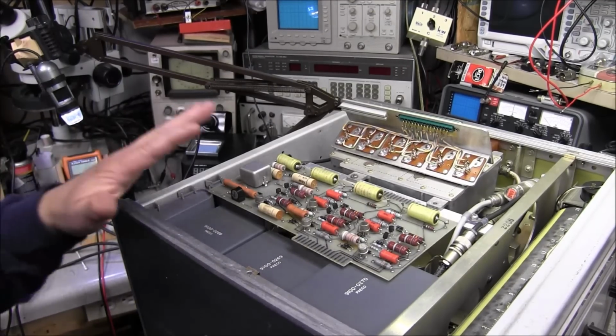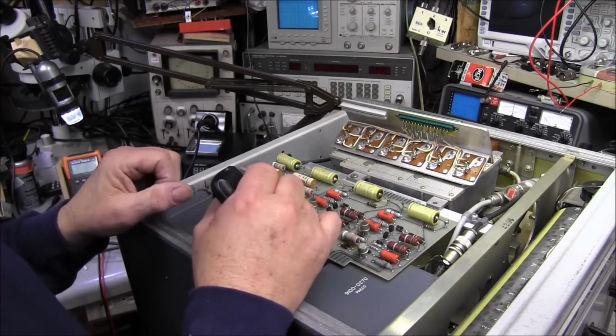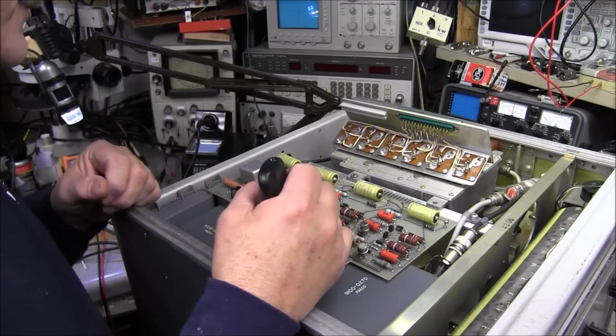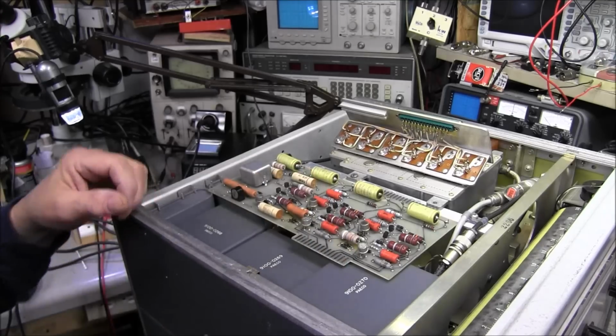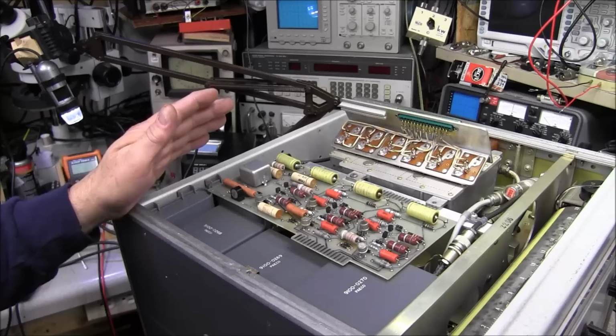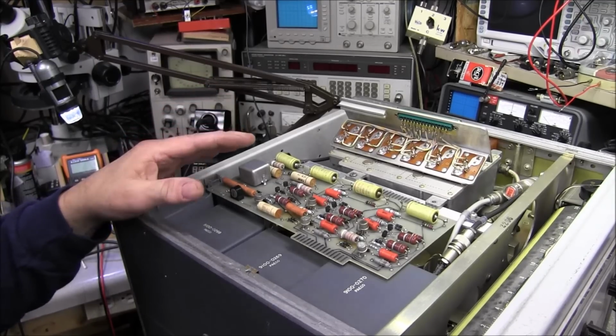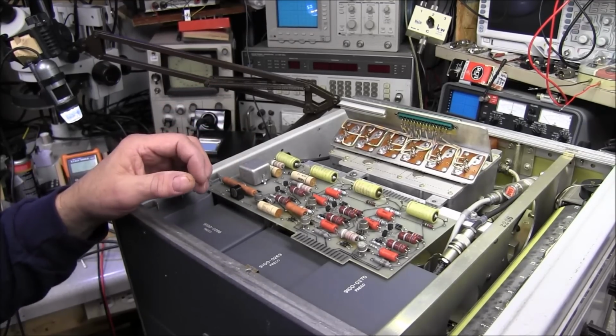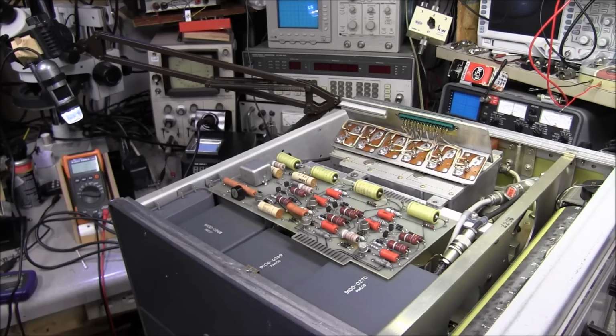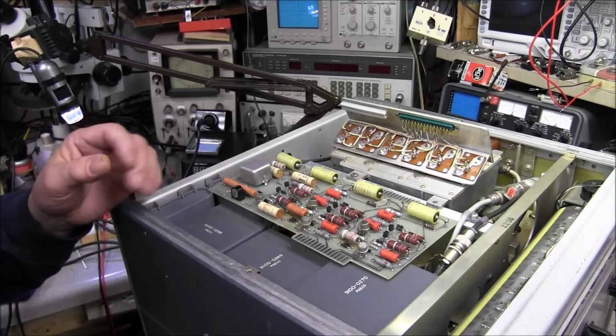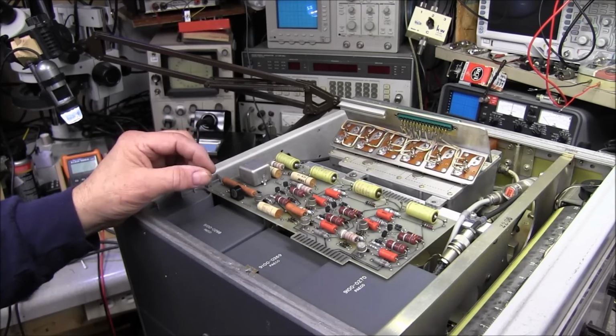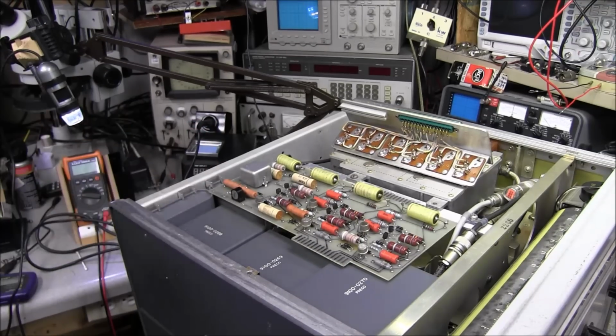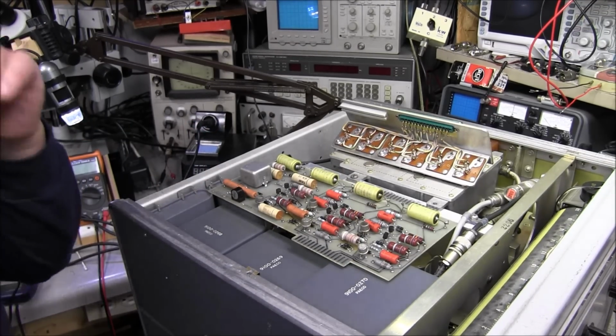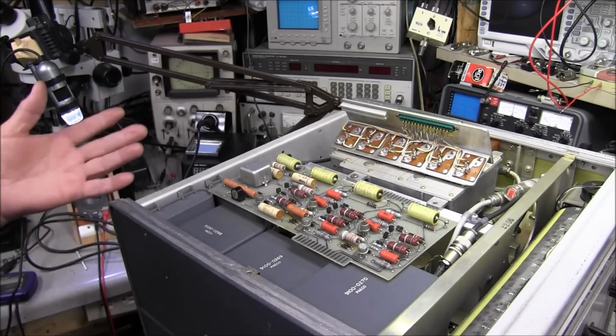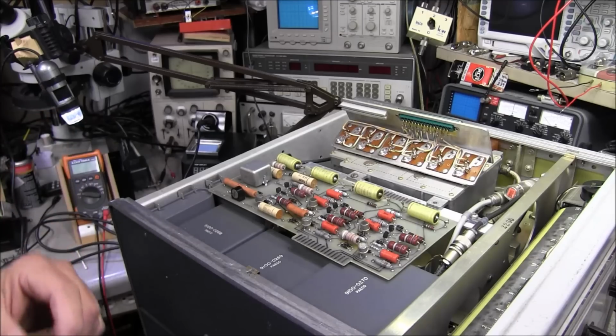So that you know where we're at, I'm doing this unit just like I did the other unit. I'm just going through it and checking some capacitors and stuff to see if I see anything that's obvious. Now on the thermistor, I do not have one of those thermistors, and like I say, that one is arcing. So what I've done, I soldered a 1/4 amp fuse across it, and that should prevent it from arcing, but if anything happens, that fuse will just go away.